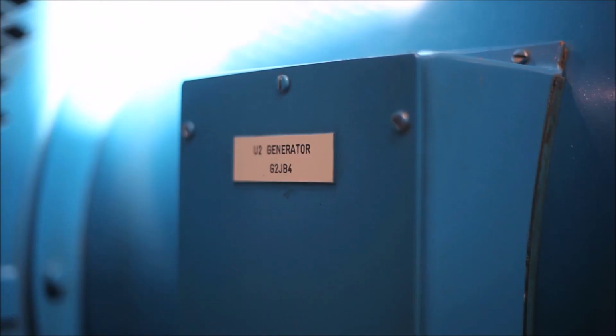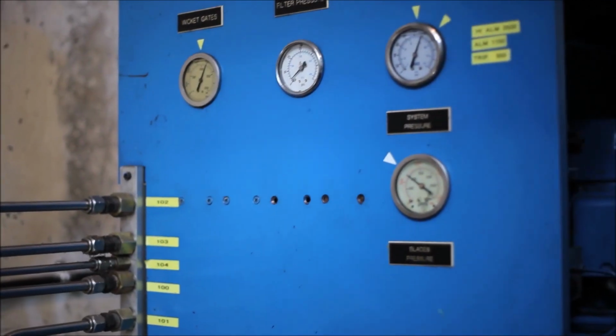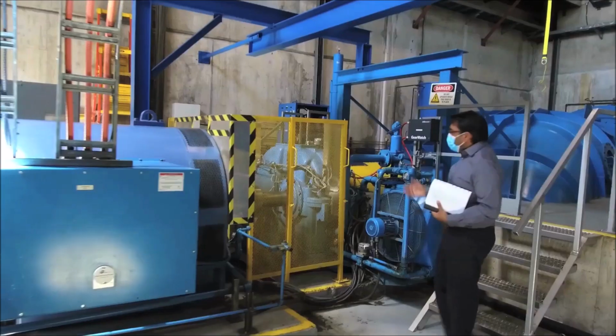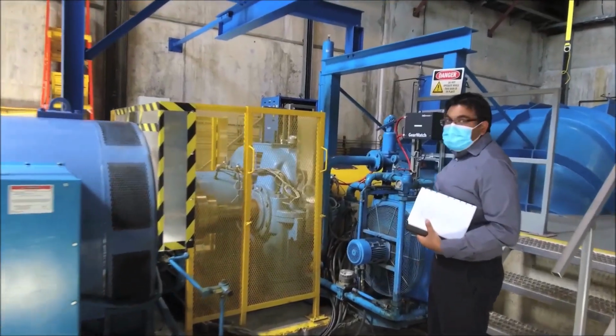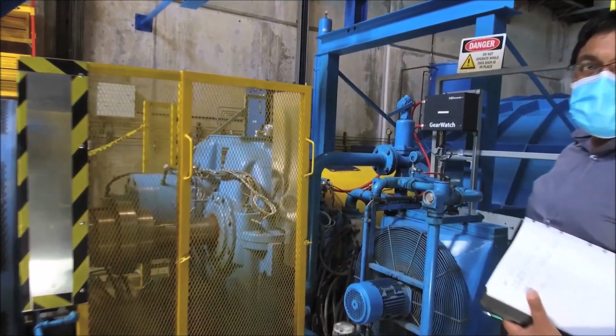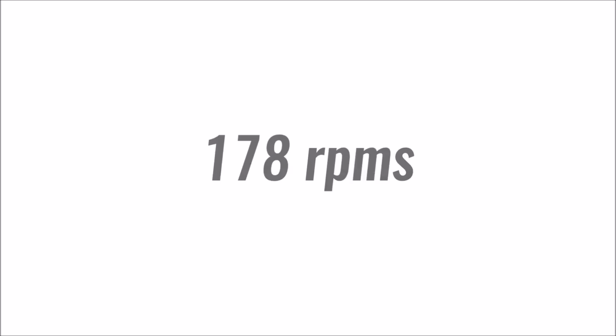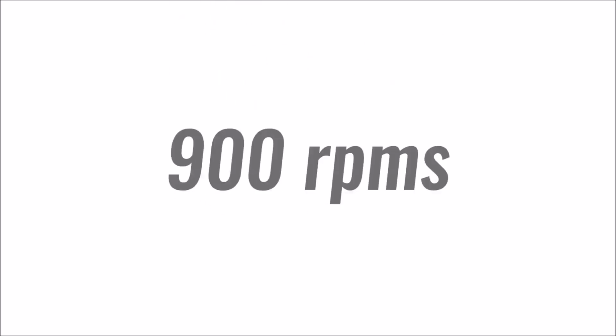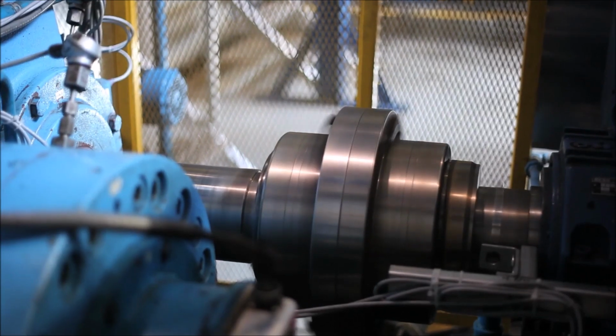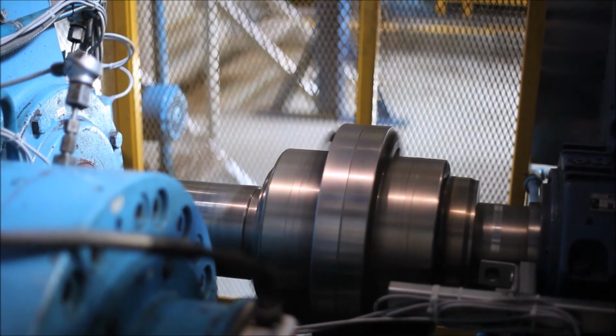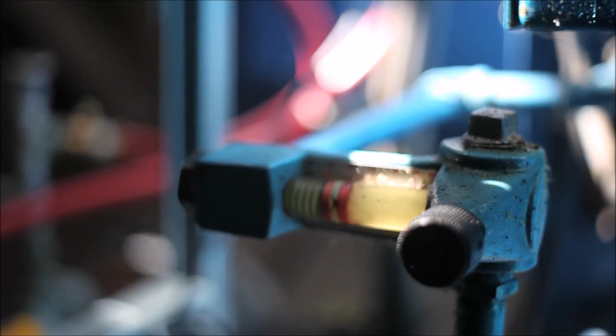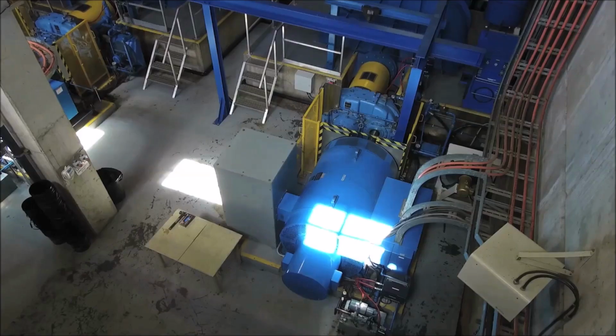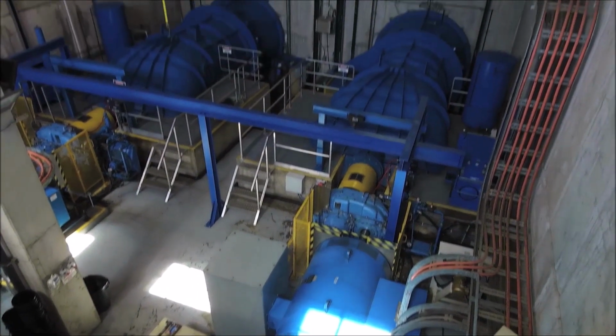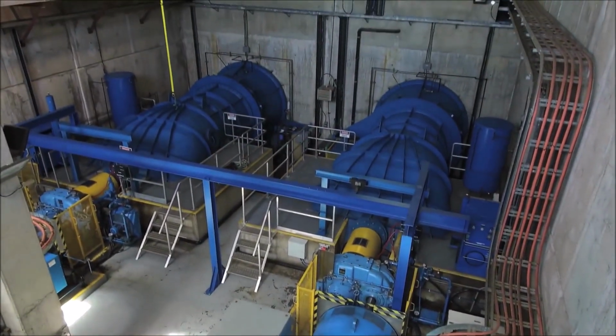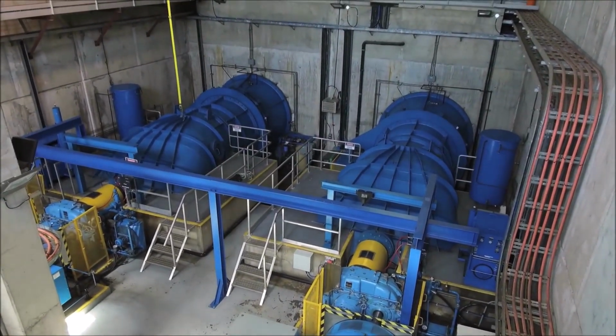The synchronous generators in Plant 2 are manufactured by Cato Engineering. The generators are connected through a gearbox, which increases the speed from 178 RPMs to 900 RPMs to reach grid synchronicity. Although this speed is required to reach grid synchronicity, it creates a lot of losses. The gearbox loses a lot of heat due to friction. We have two large radiators to dissipate the heat and keep the oil cooled.